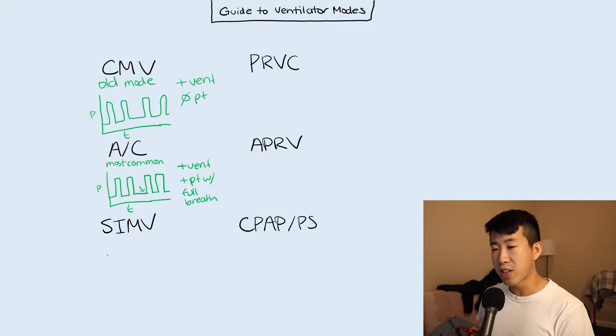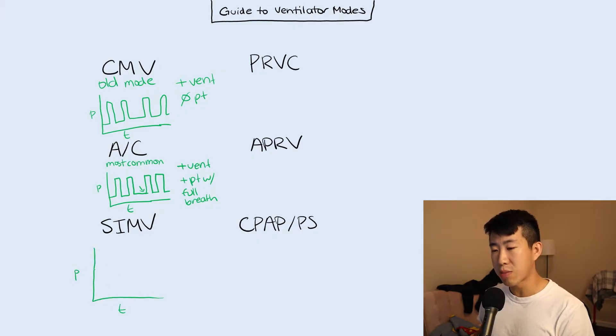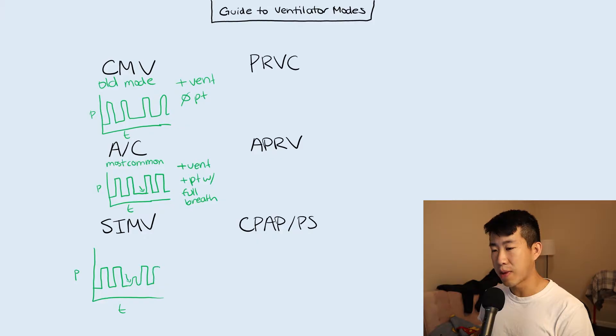SIMV stands for synchronized intermittent mandatory ventilation. This is similar to assist control, but when the patient wants to initiate a breath, it's just going to be a spontaneous breath by the patient. Say we have a couple of machine breaths and the patient wants to take a breath — they're just going to take a normal breath that's not machine-delivered, and then it goes back to the machine breath. So the patient can take a spontaneous breath at any time.